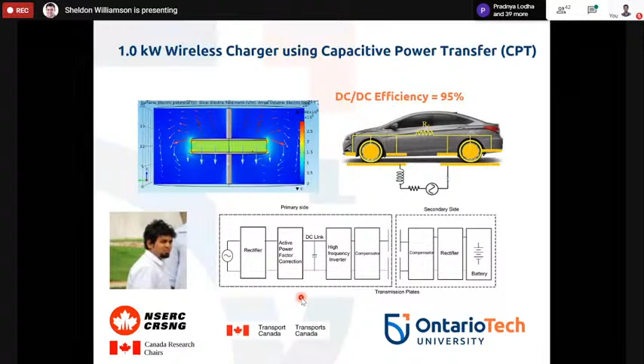We started to look at conversion stages - how to reduce the primary side to one conversion stage. On the primary side, there is low frequency AC. You convert that to DC using a rectifier, then convert to high frequency AC using an inverter. Instead of doing double conversion on the primary side, we have gone with direct AC to AC conversion using a matrix converter. Some of you may have already worked on this or have knowledge of matrix converters.